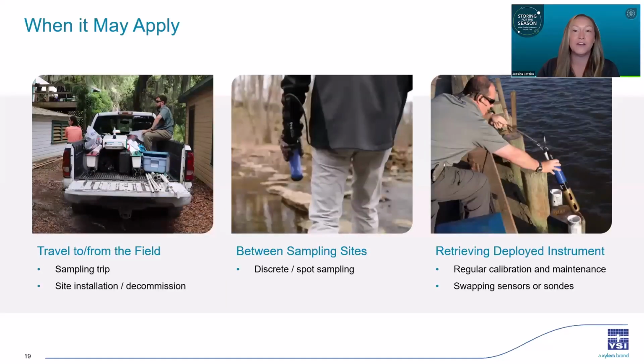Here are some examples of when you might need to store your sensor for short term. So if you are traveling to and from the field site, whether you went for a sampling trip, or bringing the equipment out for a site installation, or potentially removing it after decommissioning a site. When you travel between sampling sites for collecting spot or discrete samples. Or if you have a deployment site and you need to bring the instrument back to the office or lab to perform regular maintenance and calibrations, or even just swap out sensors or the sonde itself.